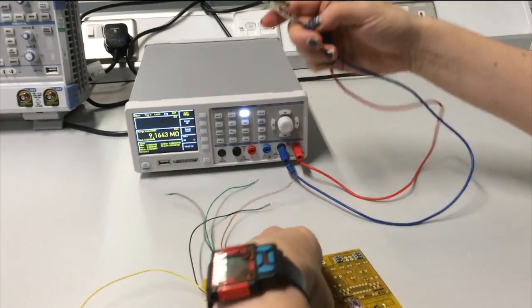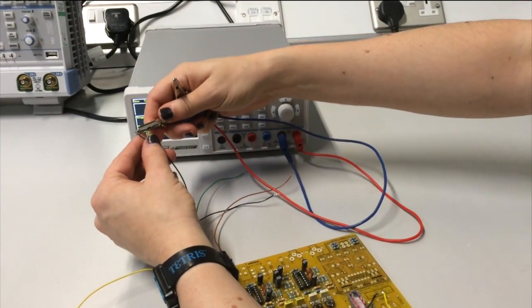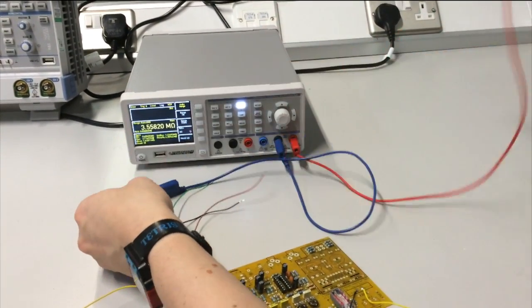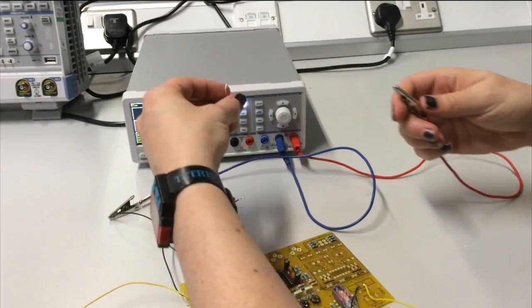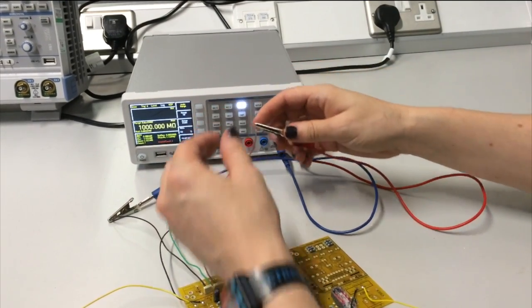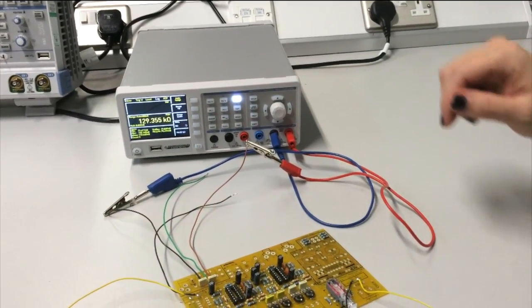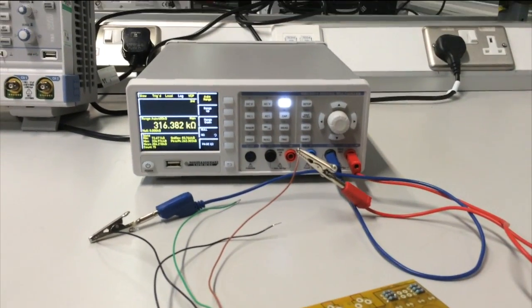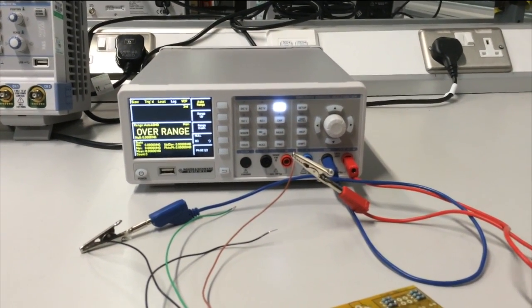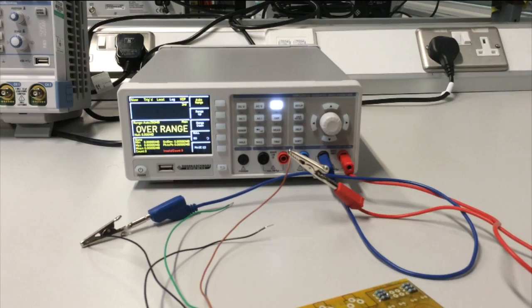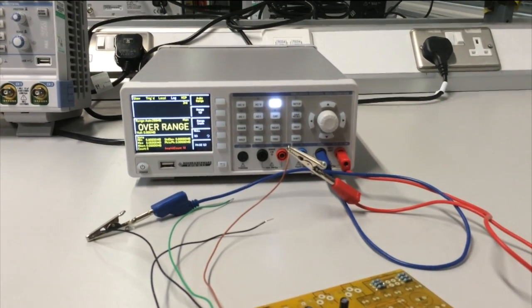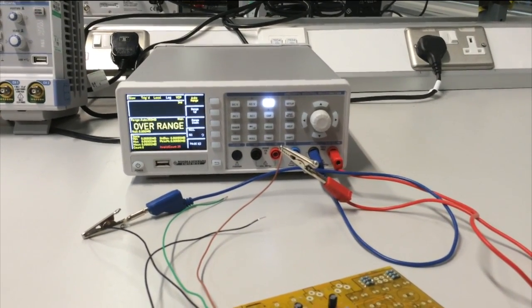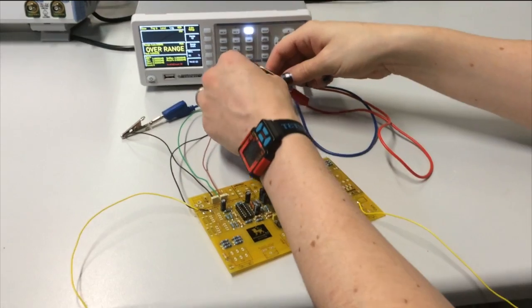So, all we need to do now is I'll use the crocodile clip onto minus 15 volts, and also clip it onto plus 15 volts. And you can see the resistance reading there. Nice high resistance, and it's going over range, which means it's higher resistance than the unit can take at all, which is brilliant, just what you want.